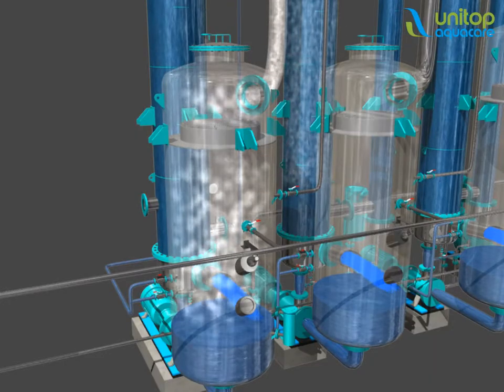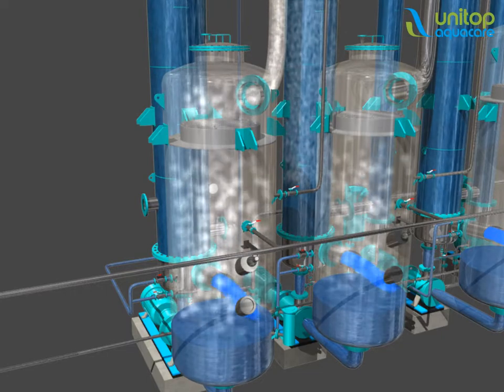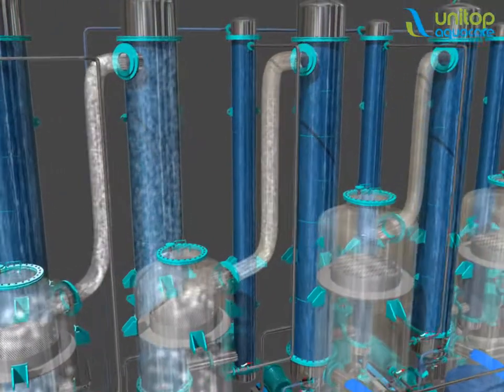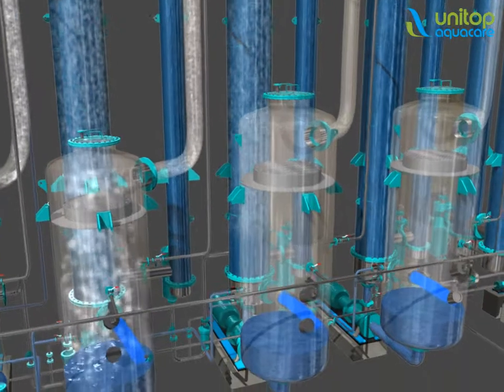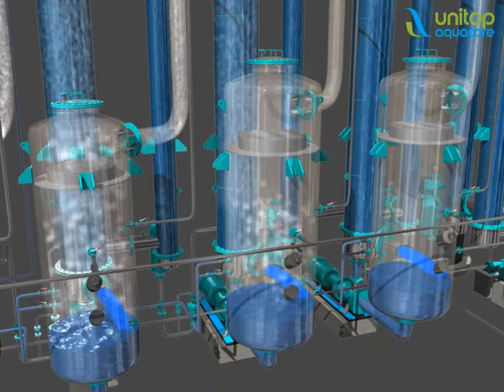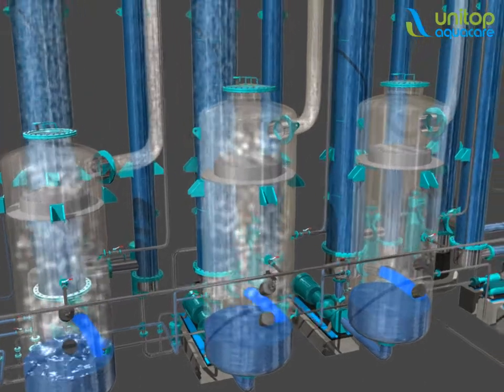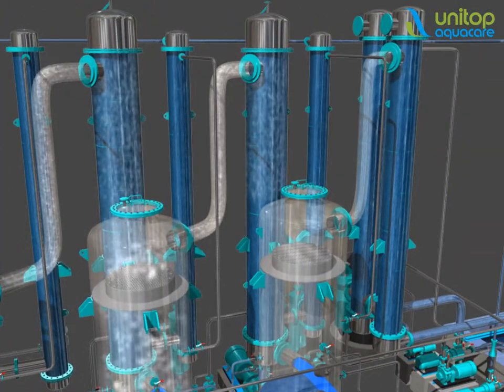In the first flash vessel, some water from the RO reject gets flashed and is converted into vapors. These vapors are carried into the next heater's shell side as a heating media by vacuum. Again, the RO reject passes through the tube, and thus there is heat transfer between shell side vapors and tube side liquid.